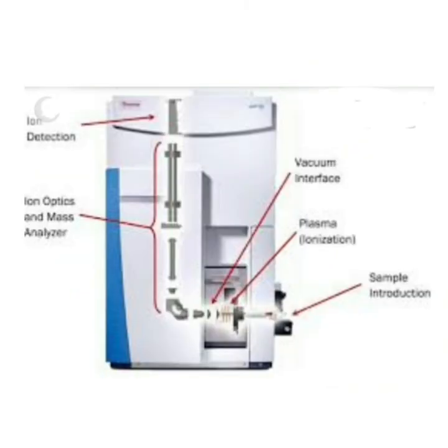Now I will introduce the original instrument, and when you go into the laboratory you will see this exact Thermo ICP-MS. In that one I can show you the parts. First is sample introduction. You can see in the image where the sample introduction is. After that, plasma ionization. In the plasma all the ionization is going on, reactions also are going on. All four types of ionization I told you about are going on there.